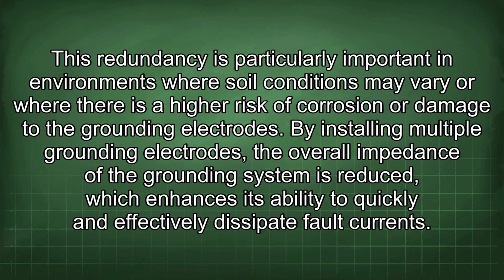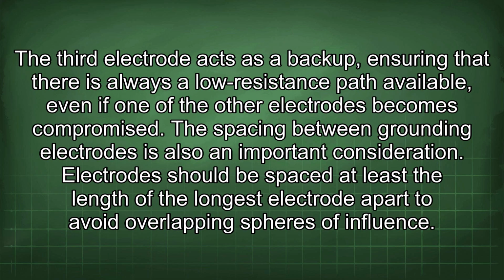This redundancy is particularly important in environments where soil conditions may vary or where there is a higher risk of corrosion or damage to the grounding electrodes. By installing multiple grounding electrodes, the overall impedance of the grounding system is reduced, which enhances its ability to quickly and effectively dissipate fault currents. The third electrode acts as a backup, ensuring that there is always a low resistance path available, even if one of the other electrodes becomes compromised.